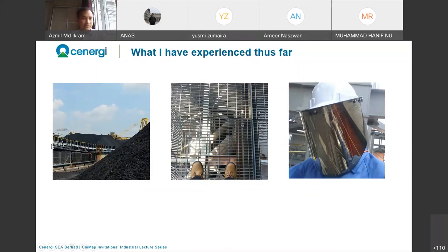So one of my analyses as a coal consultant is to see the gradient of the stacking, because you just throw the coal using this machinery, and then you need to see the integrity of the coal being stacked. If it starts to slide, that indicates the type of coal that you will get, and the combustion performance that you will get when you put it in the boiler.